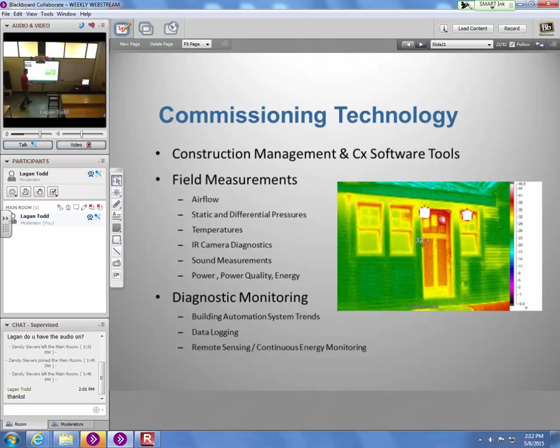We're working a lot with the building automation system, using that interface to test the systems and observe operation, as well as commissioning the interface itself. So I'm looking at the graphics and asking, are all these labels correct? If they've got a temperature sensor on this panel, why isn't the temp shown there? I'm commissioning the interface so that when the owner starts using it, it's as accurate, complete, and user-friendly as possible.